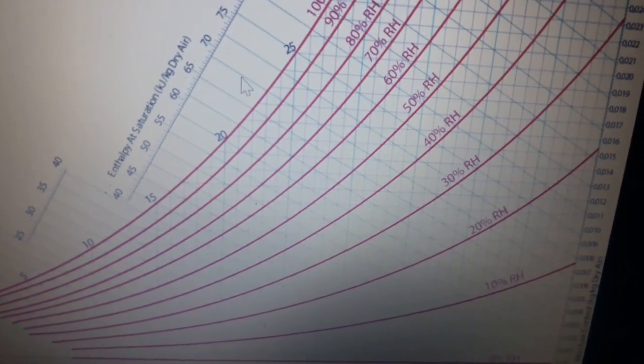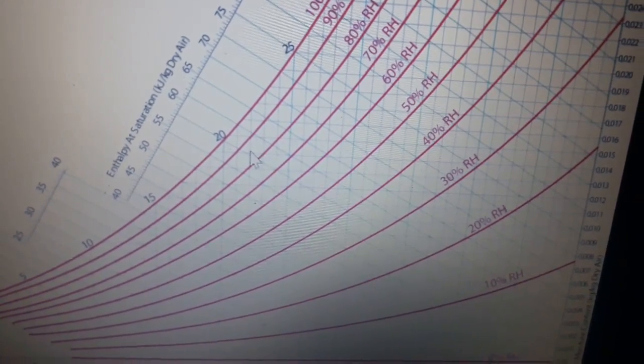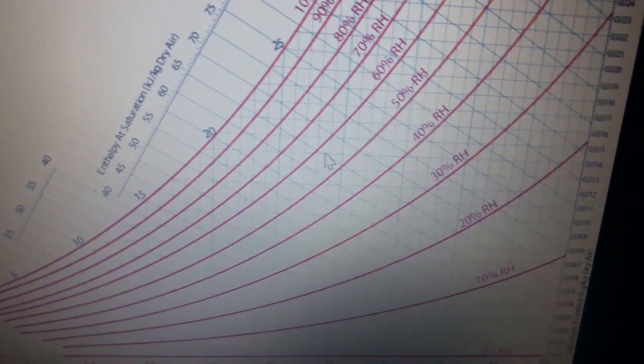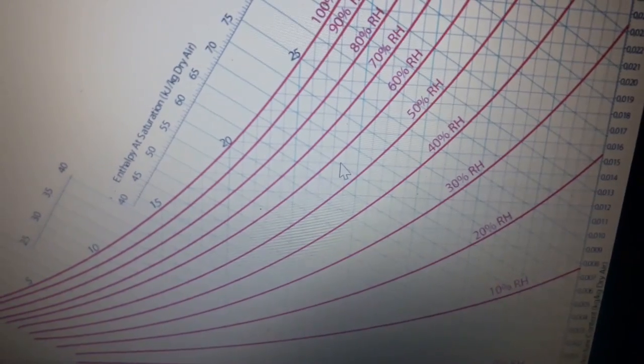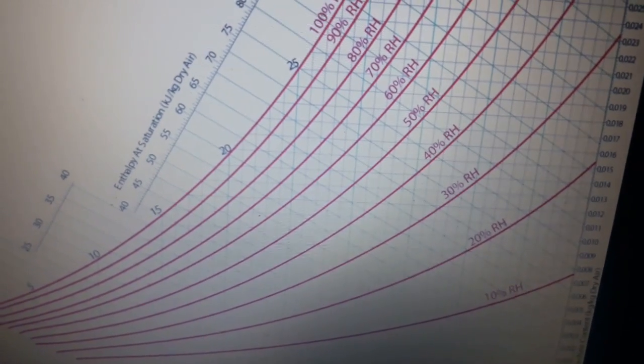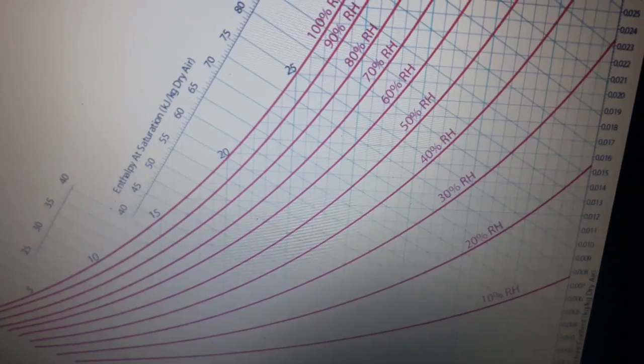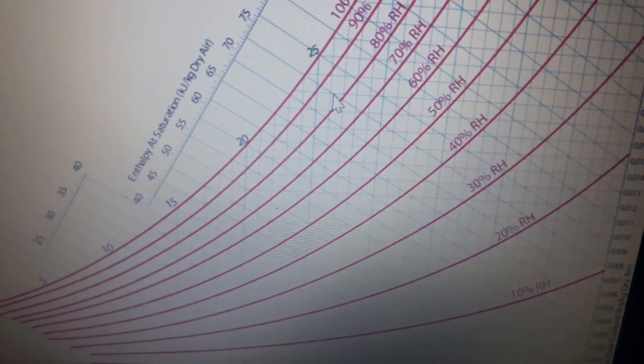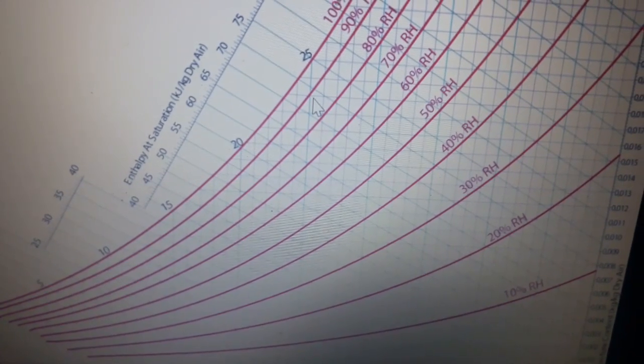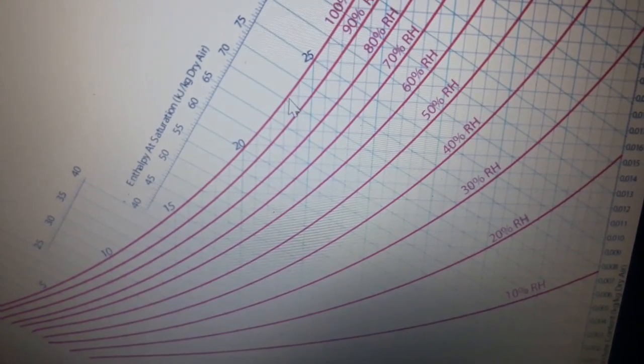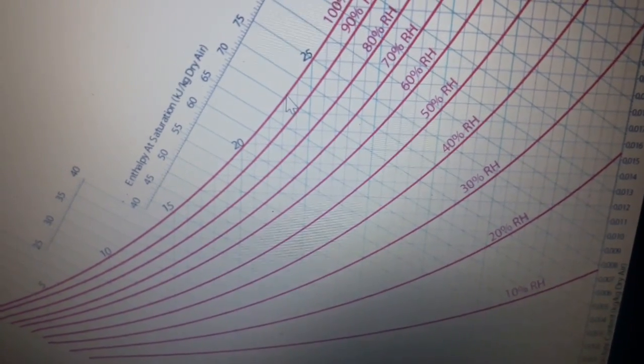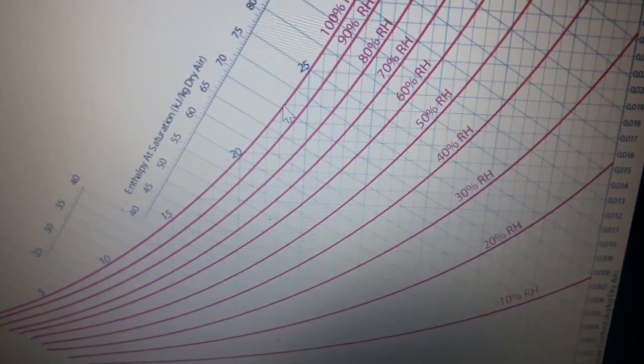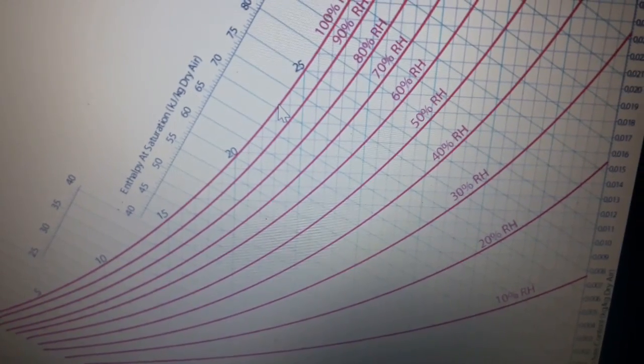For specific volume, the simplified chart doesn't clearly show the specific volume lines, so we will move to that shortly. For apparatus dew point: extending the process line to meet the saturation curve, it meets near 23°C, so ADP = 23°C.